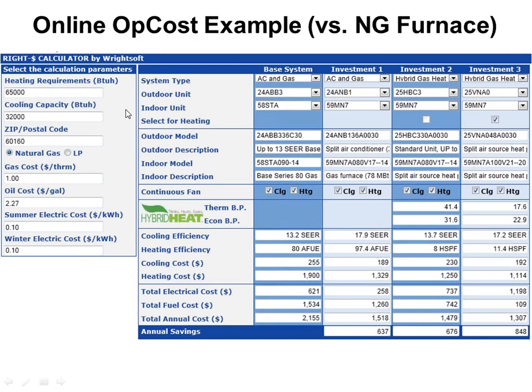I did some screenshots here of natural gas, propane, and electric customers, so you can see all 3 of the outputs. So you put your heating and cooling loads in on the left-hand side. Now these are the loads you put in, not the size of the existing furnace. So if somebody has a 100,000 BTU furnace, you don't put 100,000 here. If it's a 100,000 BTU furnace at 80%, you'd put 80,000 here. And then hopefully at some point you actually do a load calculation and find out what the real load is and then put that in here.